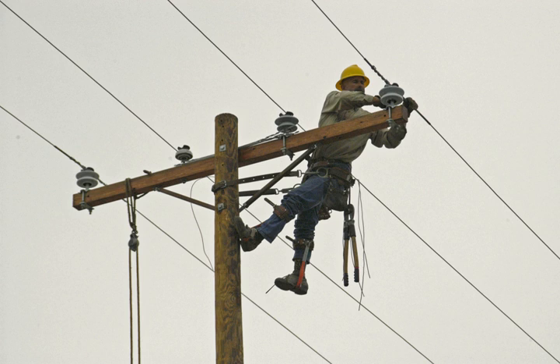High-voltage transmission lines can be worked live with proper setups. The lineman must be isolated from the ground. The lineman wears special conductive clothing that is connected to the live power line, at which point the line and the lineman are at the same potential, allowing the lineman to handle the wire. The lineman may still be electrocuted if he completes an electrical circuit, for example by handling both ends of a broken conductor. Such work is often done by helicopter by specially trained linemen.